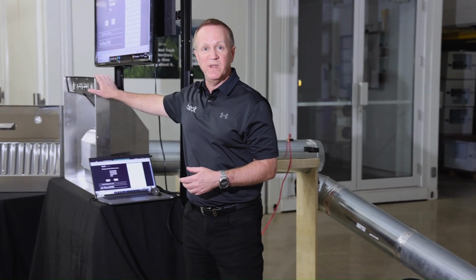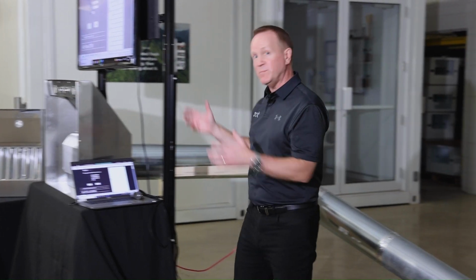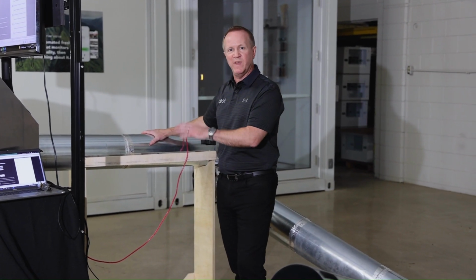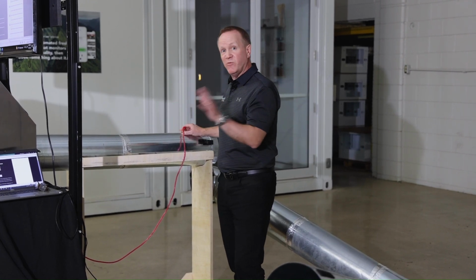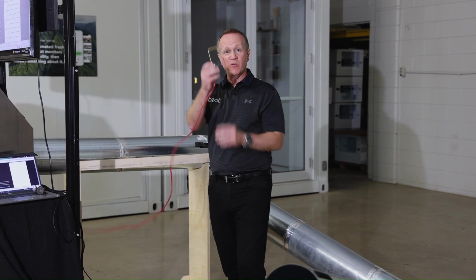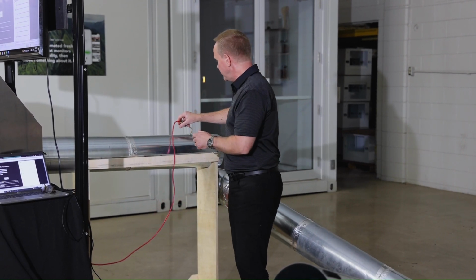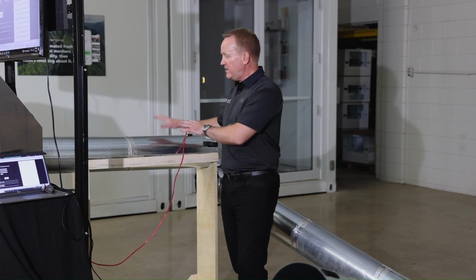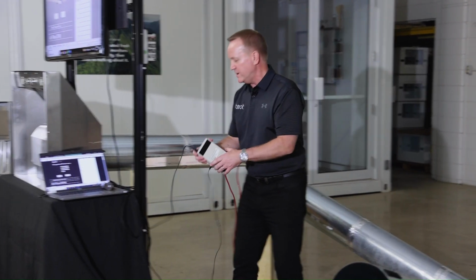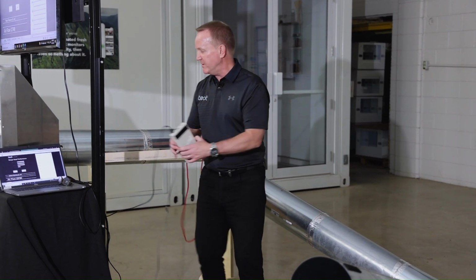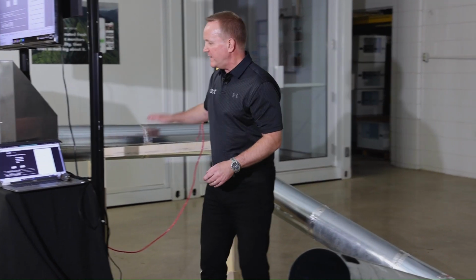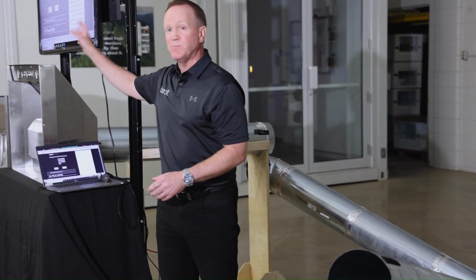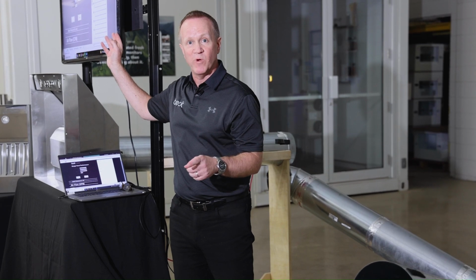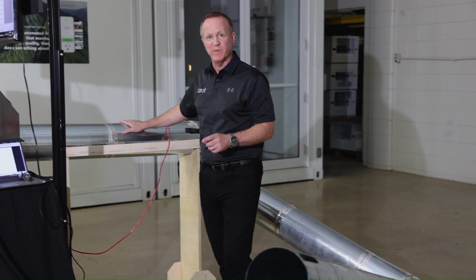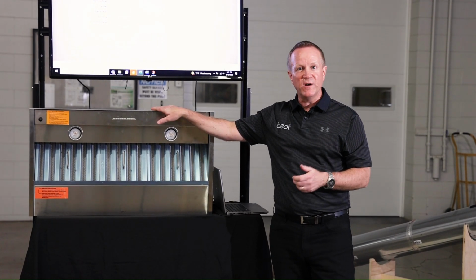Here's how we're going to do our competitive comparison. We're going to put each of those 3 hoods on this counter, and hooked up to that hood is going to be about 4 feet of 8-inch ducting, and in that 4 feet of ducting I've got an airflow probe that is measuring the amount of resistance that is being generated in that duct run, and that is going to my airflow gauge that I got right here. And then that is tied into this laptop, which will then display it on this screen how that hood is actually performing.